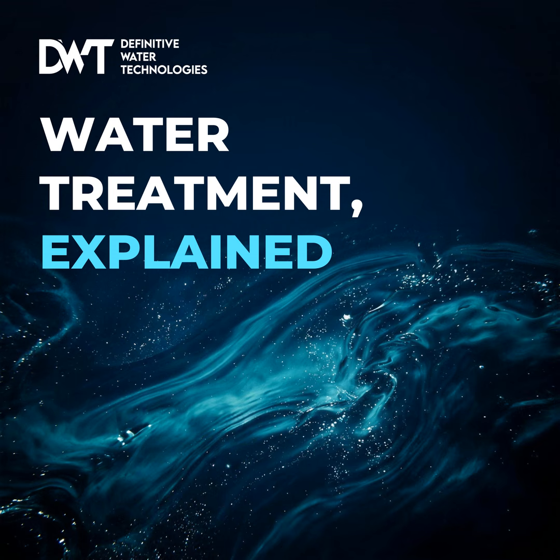No, not at all. You don't change the hardware. The secret, and the cheapest fix on any site, is dilution. You change the fluid to match the machine. If we take that concentrated antiscalant and dilute it 10 to 1 with water in a day tank, our required duty jumps from 0.06 to 0.6 liters per hour, which puts us at 12% of our 5-liter pump. Getting closer.